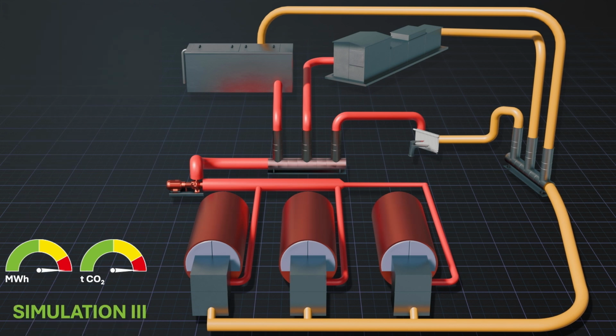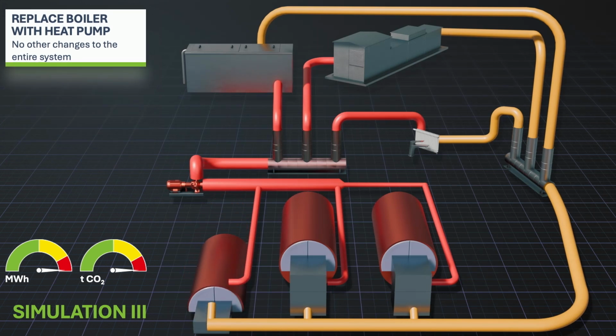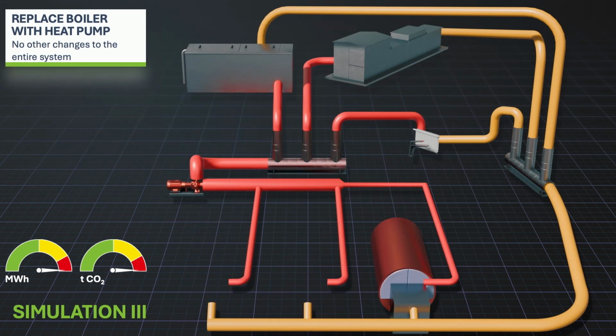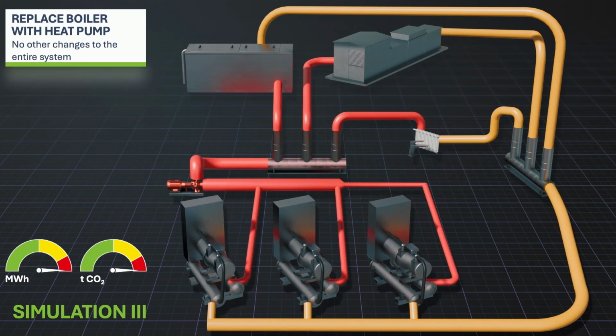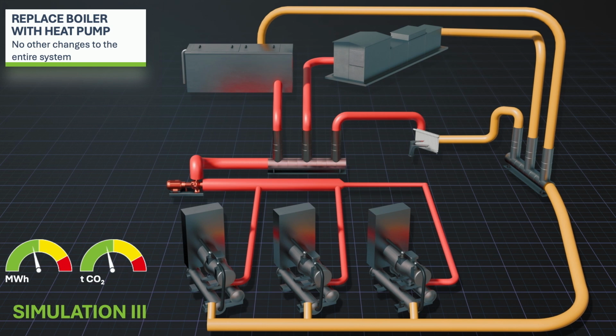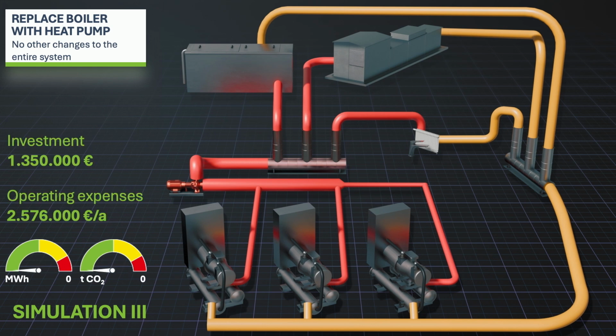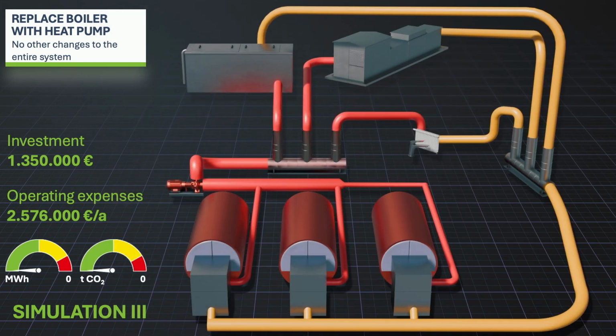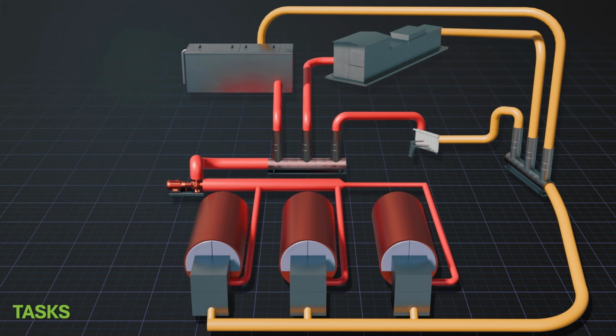The existing gas boilers could also be replaced by high-temperature heat pumps. This also reduces CO2 emissions, but both the investment costs and the operating costs are higher than with the first option. Here too, there is no improvement in hydraulics. In order to prepare the overall system for the future, measures to reduce the heat demand are first proposed in order to then redesign the heating center according to that new reduced demand.